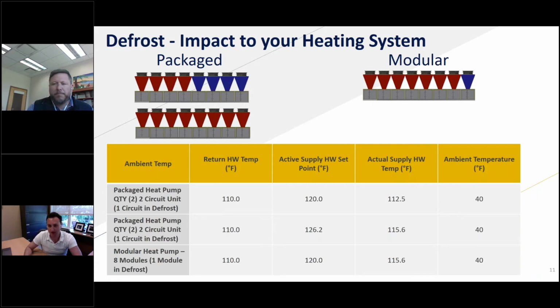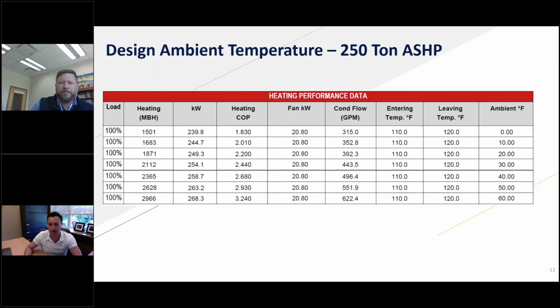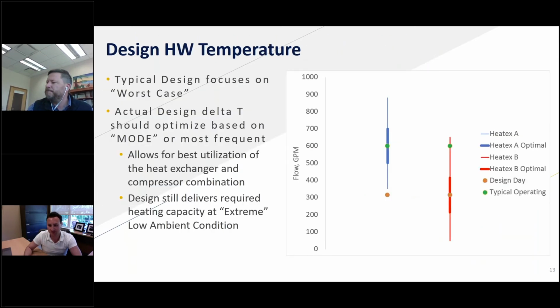Okay, couple more. What triggers defrost? I think I already answered that. It's hard to say because that's really a function of the manufacturer of the equipment. There's lots of ways to do it. At the end of the day, if you're going to be more sophisticated with your control, what we're trying to do is figure out when we actually have ice forming on coils. There are multiple factors at play that make that happen, and so it's a function of how you determine how you want to figure that out or measure that.